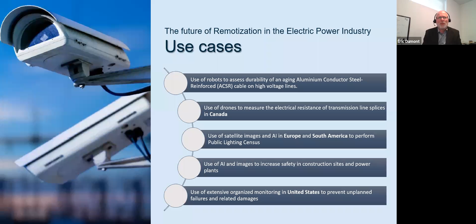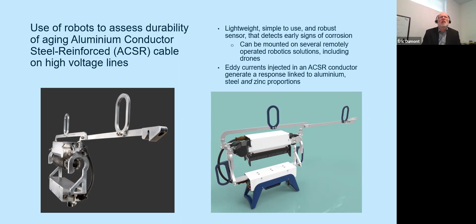We will see different kinds of remotization. The first, if we go to the next slide, please, is about a robot used to assess the durability of aging aluminum conductor. That's a robot which is lightweight, simple to use, and uses eddy current to assess the amount of zinc within a conductor, just to be able to evaluate the remaining life of the conductor. This probe can be mounted on a robot on the line. So if you can bring the other slide, please. You can see here an application of this probe on a robot used on a line that allows assessing the remaining life of the line.